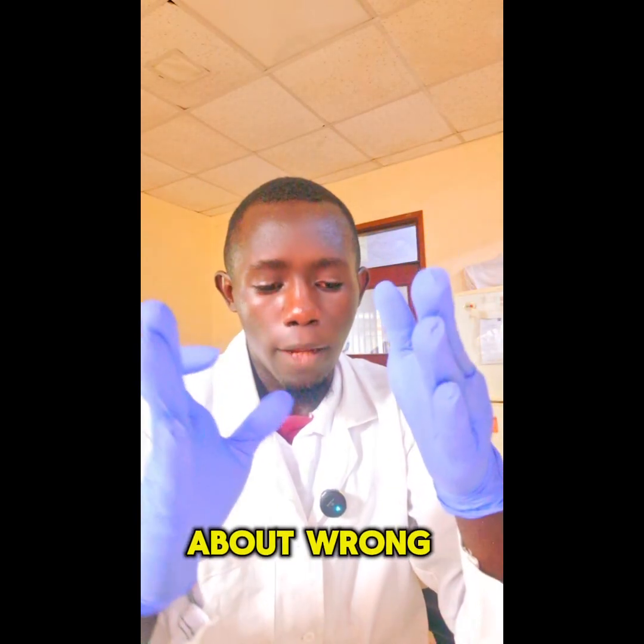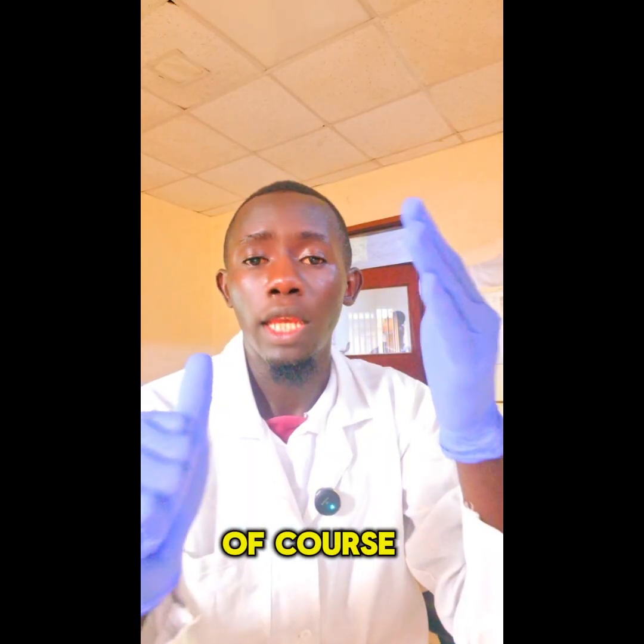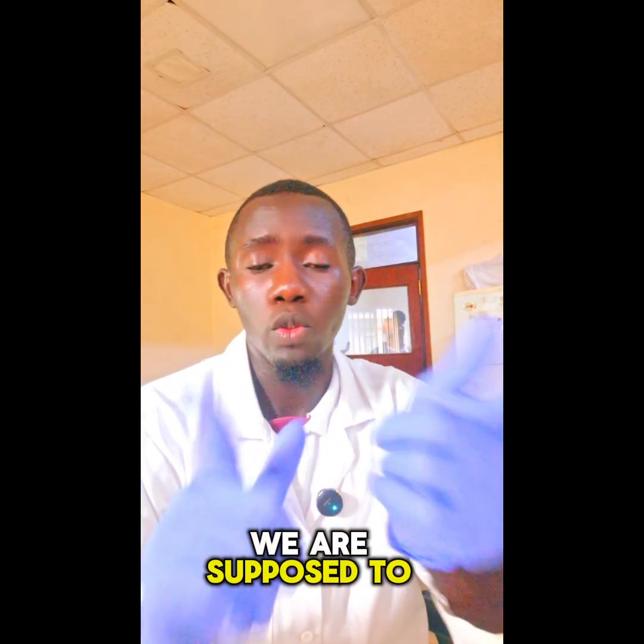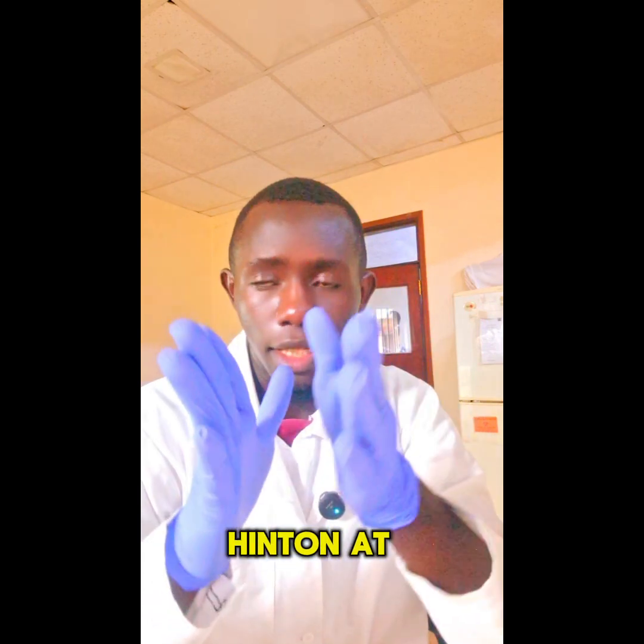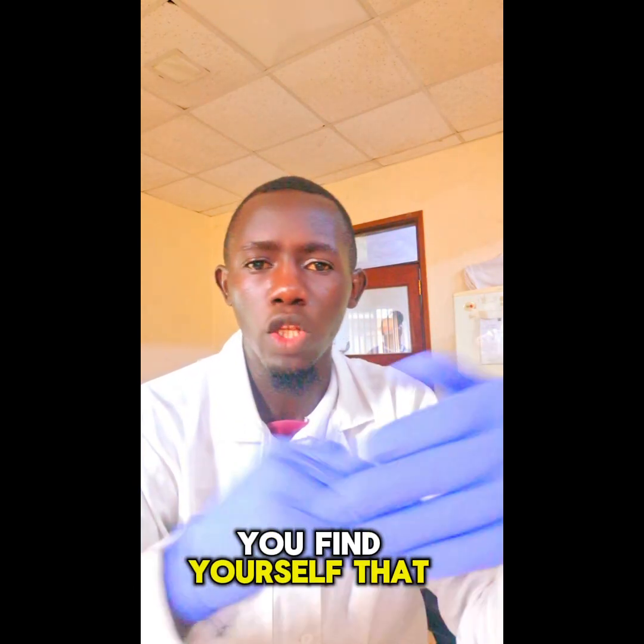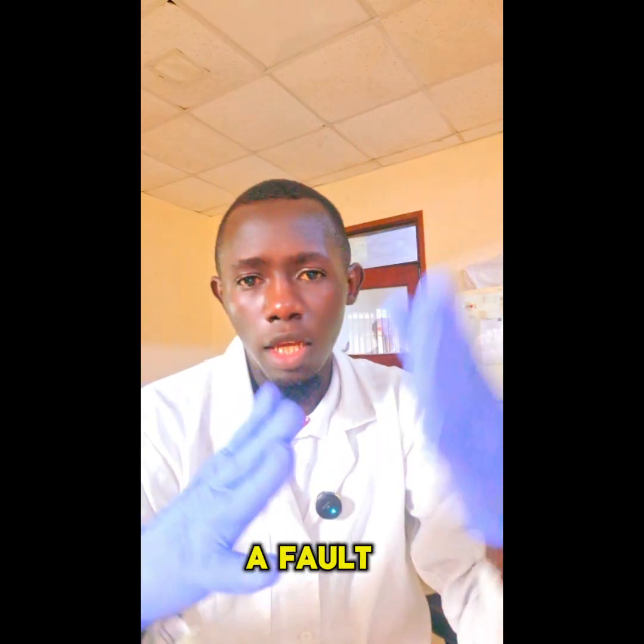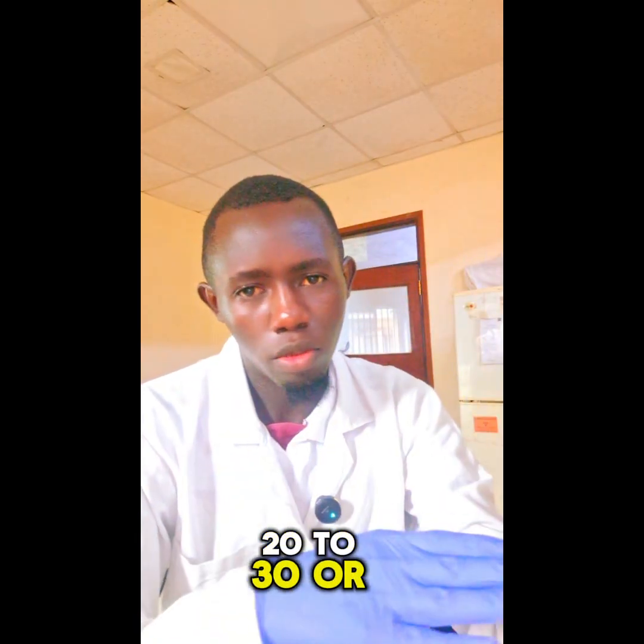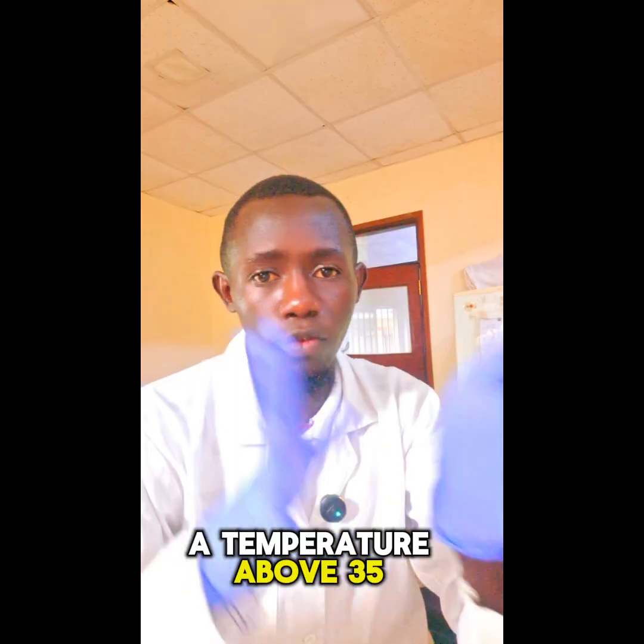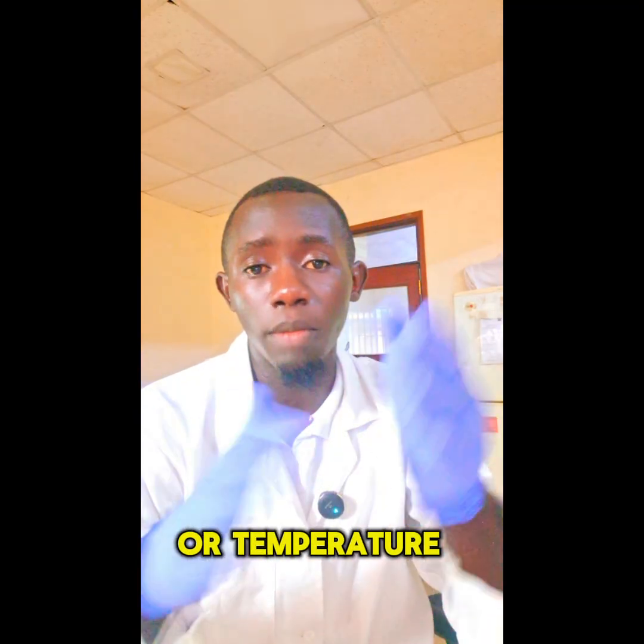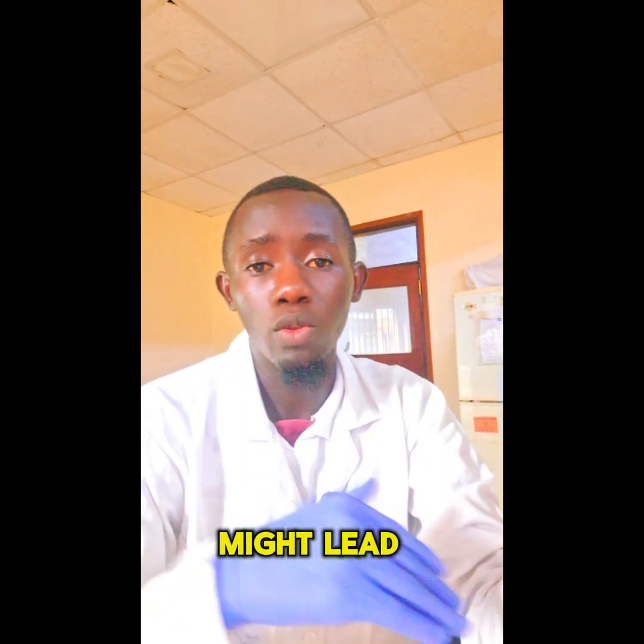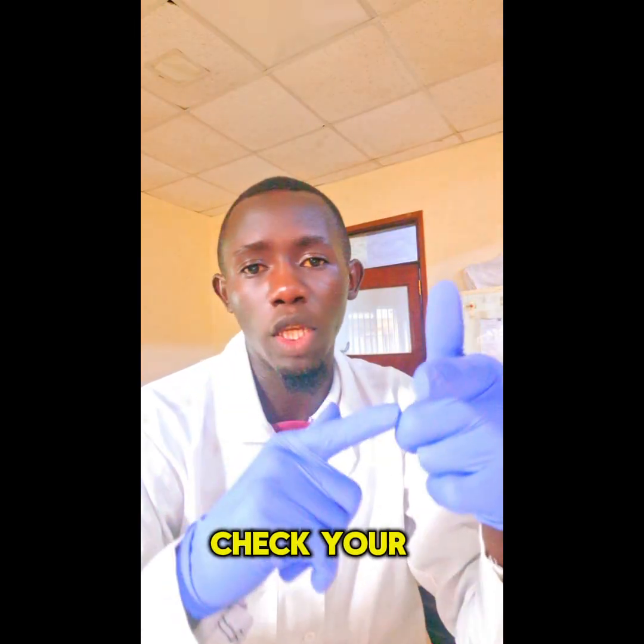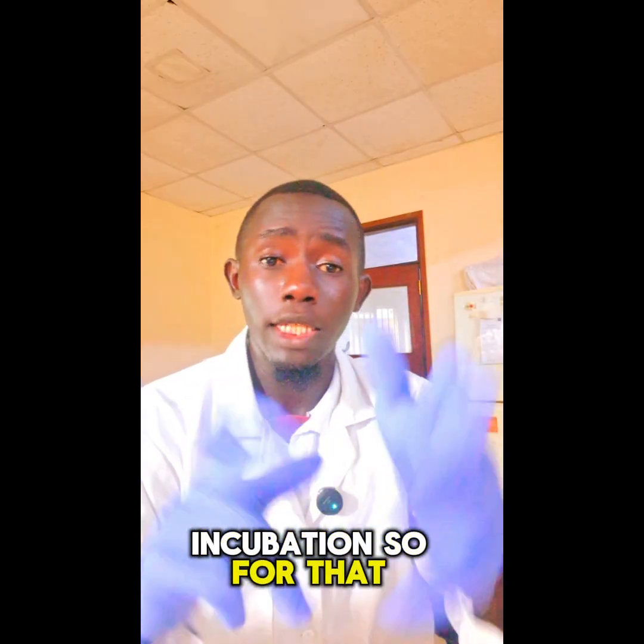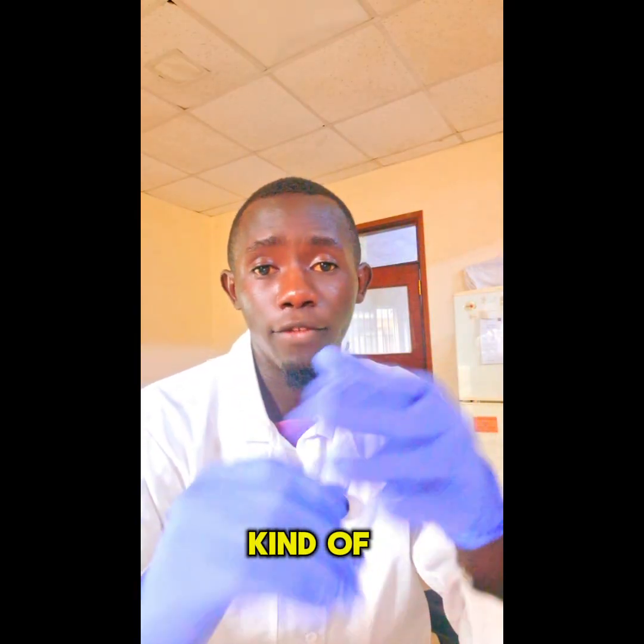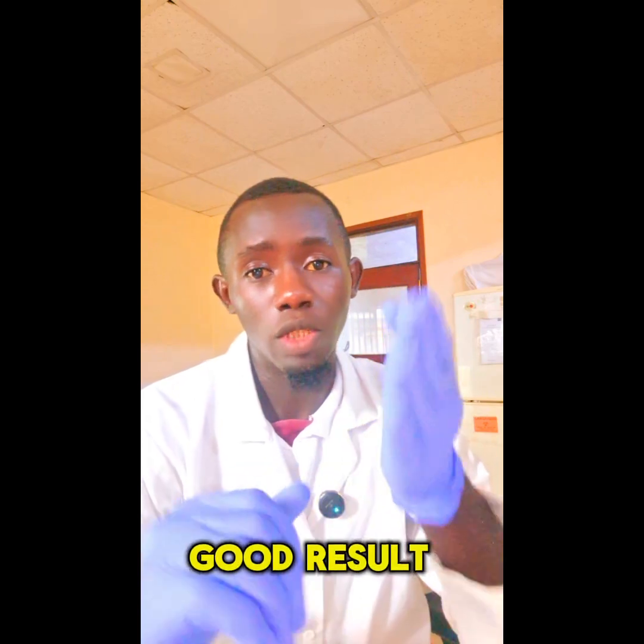The other one is wrong incubation, of course. We are supposed to incubate our Mueller Hinton at 35 to 37 degrees Celsius. You might find that your incubator has a fault, so you're incubating at 20 to 30, or a temperature above 37 or below 35, which might lead to that kind of resistance. So ensure that you check your incubator before doing your incubation. If you reduce these factors, you will get a good result.